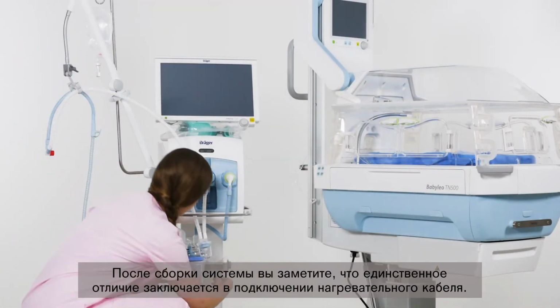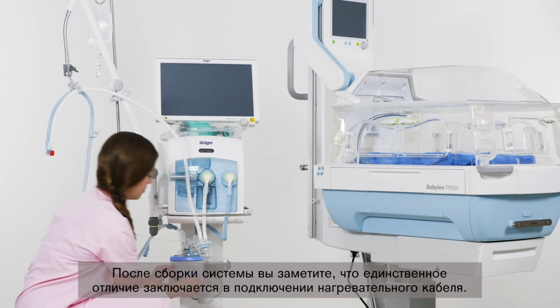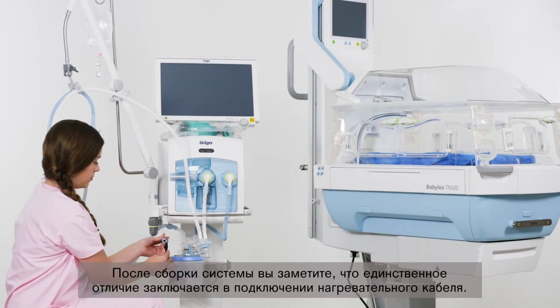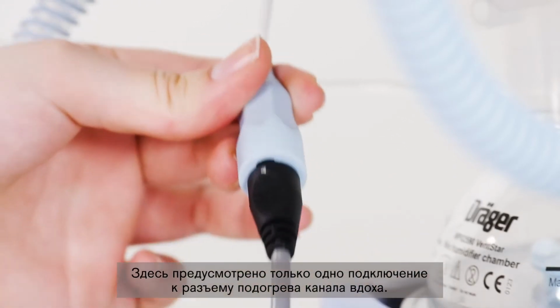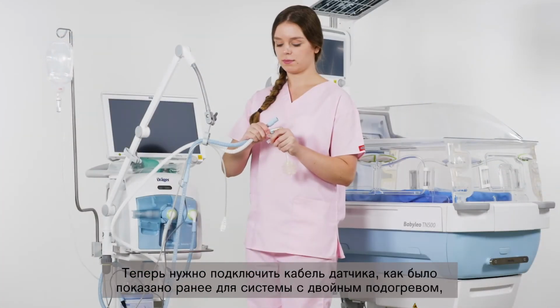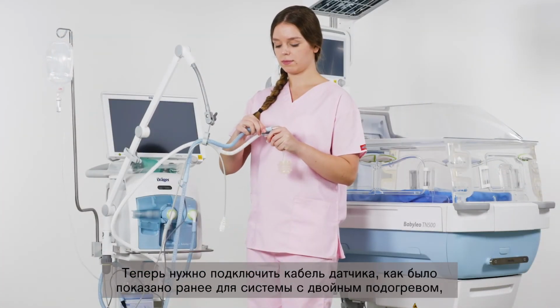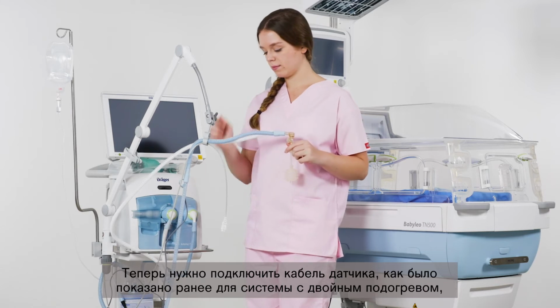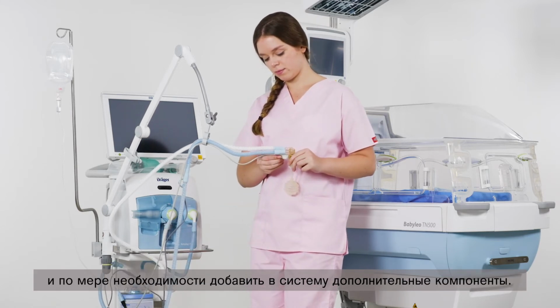After setting up the system, you will notice that the only difference lies in the connection of the heating cable. Here there is only one connection to the inspiratory heating connector. You should now connect the sensor cable as previously demonstrated for the dual heated system and add further components to the system as required.